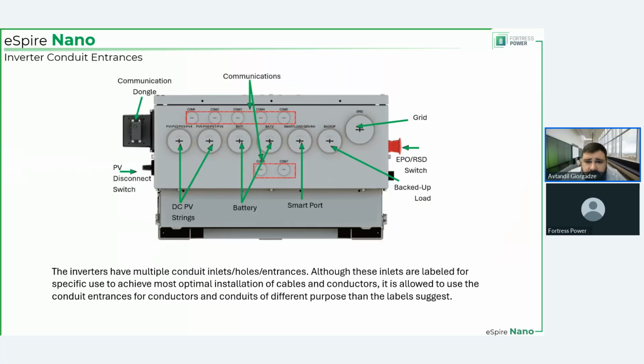Now, the ports. These are the ports. They are labeled for what they are, but it's not mandatory. Well, the ports are mandatory to be used as they are labeled, we're going to see that in a moment. But the inputs you can use differently if you want, depending on your application and what you're trying to do. So use them as you need to, to some extent. If you use the inverter mounted on the exterior wall of our outdoor unit, some of it is predetermined for you. These three will be occupied by default, and these two will be reserved for PV, and then you have backup and grid. So not much choice, but it doesn't matter to us which input you use for what.